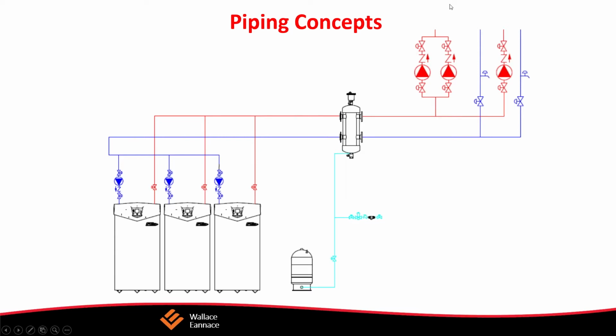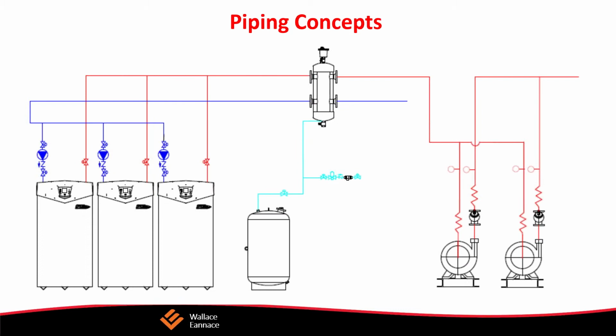But a better alternative to that is a two-pipe reverse return. Now, what's going to happen here is, as you can see, the first one out is the last one back. That's reverse return: first one in, last one out. It's more expensive, it's easier to zone, has equal delta T, and the other big advantage is that it guarantees the radiators will all get equal flow.